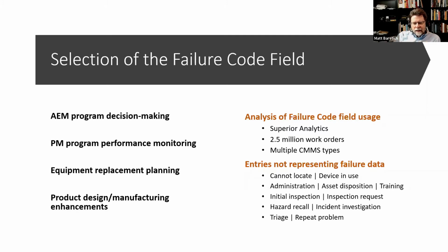So we said there are a lot of things in there that have nothing to do with failure. For example, cannot locate device in use. Absolutely, we have to keep track of that, because that's data we use when we're calculating PM completion percentages. But it's not a failure. So our thought is that it goes in a different field. It doesn't go in the failure code field. And you can see some other things that are very useful pieces of information to track, but it's not about failures. So the first thing we started out with was to say we're going to recommend using the failure code field just to record equipment failure types.